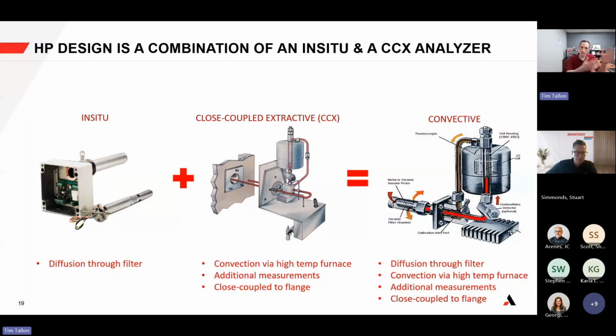All right, well, putting it together, the benefits of an in situ type with the benefits of close coupled extractive type, you get what we call the convective type. The convective analyzer uses a combination of both. There's diffusion through the filter, similar to that of an in situ, but there's added motive force of this high temperature furnace. And that high temperature furnace is that convection. Just as the convection worked in a close coupled extractive, that convective type is also pulling the sample in. So in addition to diffusion, there's the convection, the heat of that furnace that's pulling up and creating a flow, even with particulate, up and around and back out.